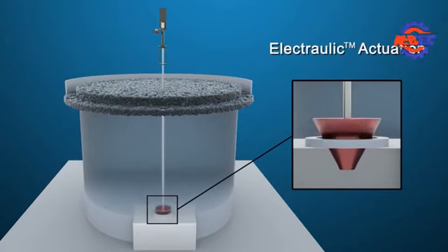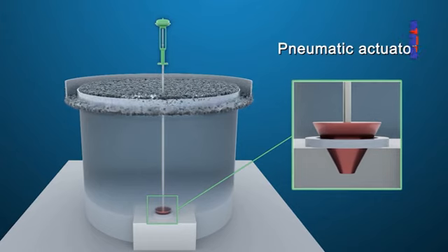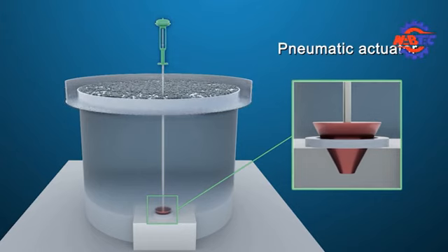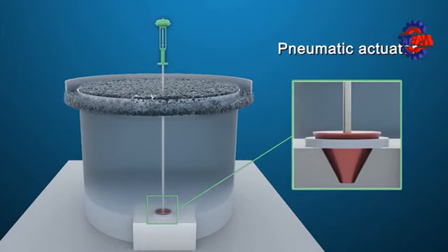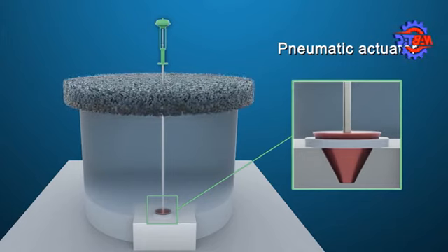If the valve response time is sluggish and slow to close, the tank level will decrease, resulting in less froth entering the launder. If the valve stalls in a closed position with a pneumatic actuator and does not open when commanded by the control signal, the froth and pulp will overflow and spill to the ground, resulting in expensive cleanup and reprocessing.